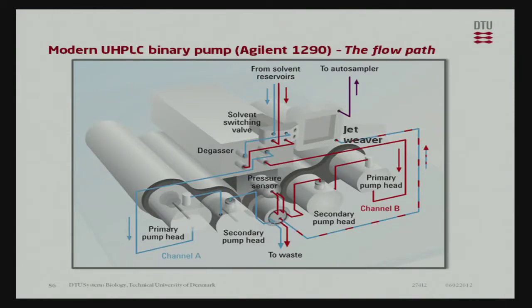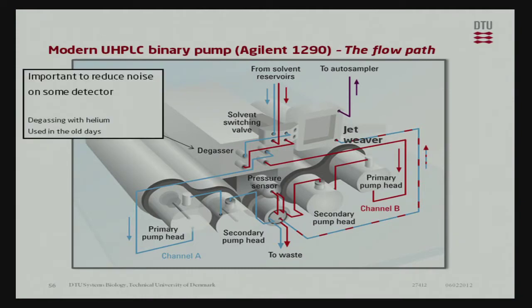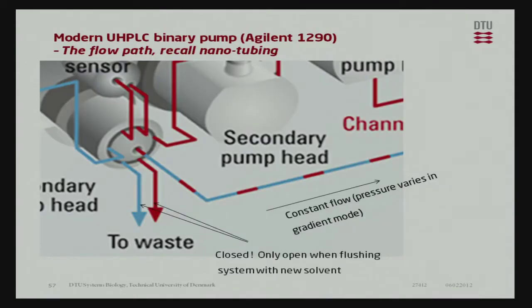So, usually most pumps have two pump heads. So, the pump head A that goes faster here in the pistons, and then the second one that goes half the slow, half the speed. And then they are then mixed. And also the degasser is very important. If you have old HPLC system, you may see that you sparge the solvent with helium.